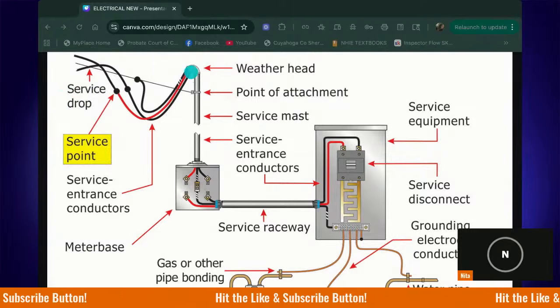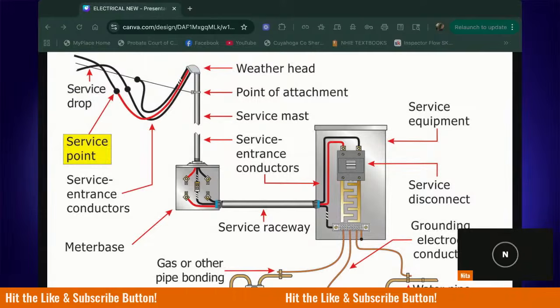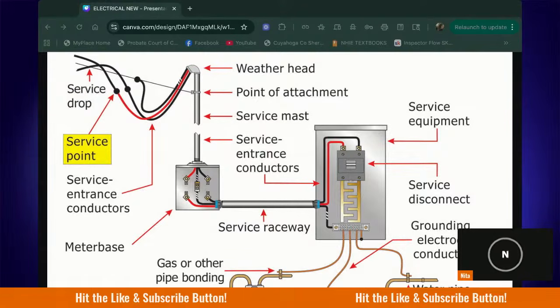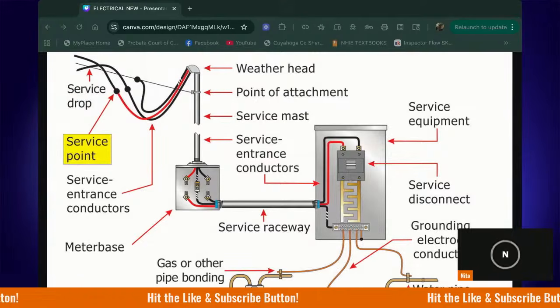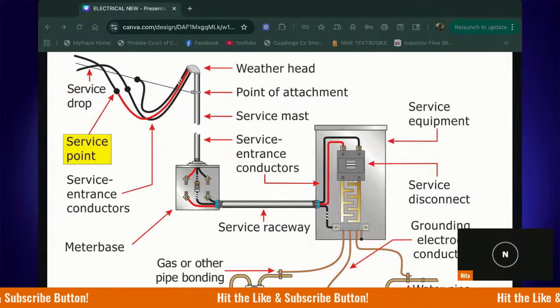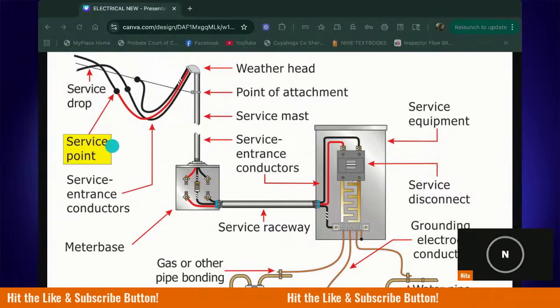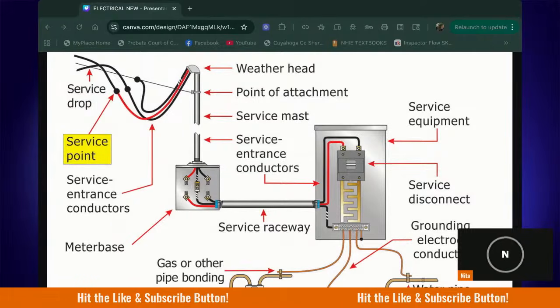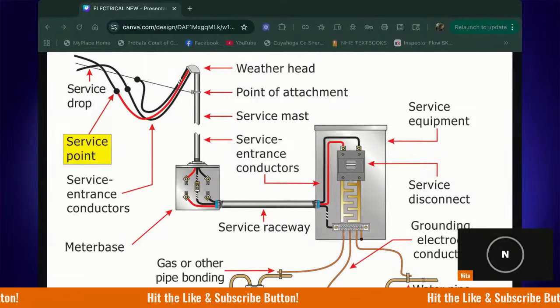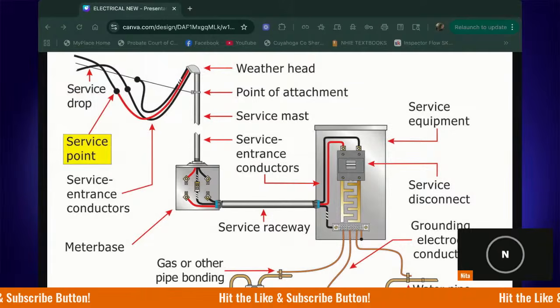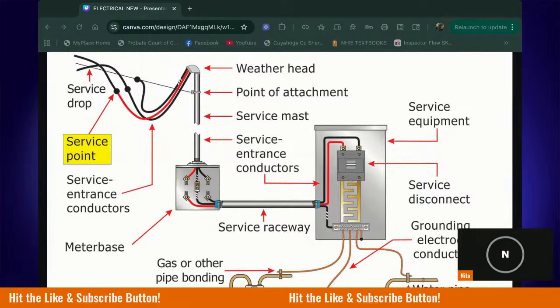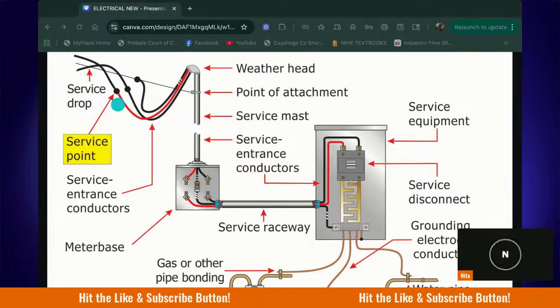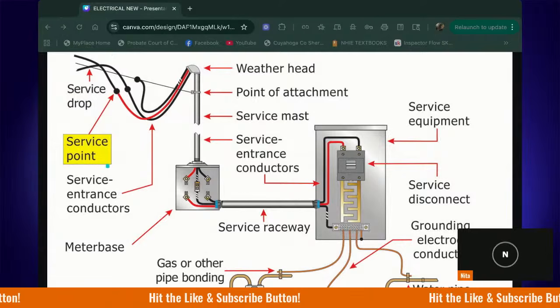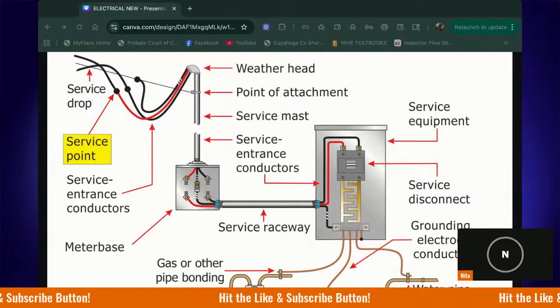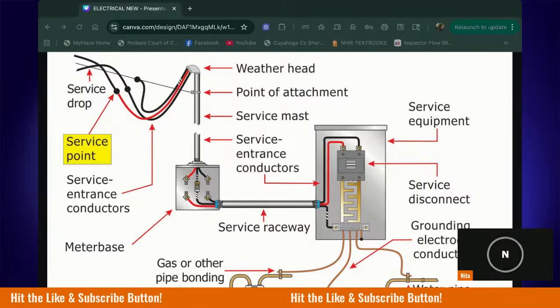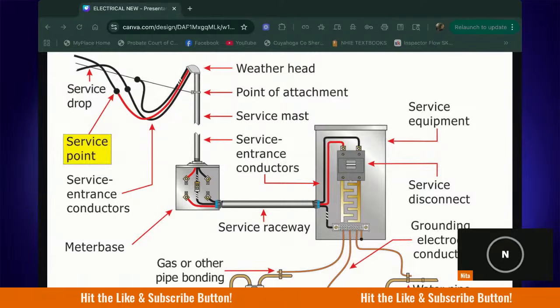These service entrance conductors pass through a weatherhead or a gooseneck before they go down the service mast. A service mast is just conduit to protect the wires. One thing to note, before the weatherhead, newer requirements call for a drip loop. This is literally a drooping or downward loop of the wire right before it goes into the weatherhead. The idea is that this allows rainwater to drip off the cable before it goes into the weatherhead. So at step 4, you now have service entrance conductors, a drip loop, a weatherhead, and the conductors going down the service mast.